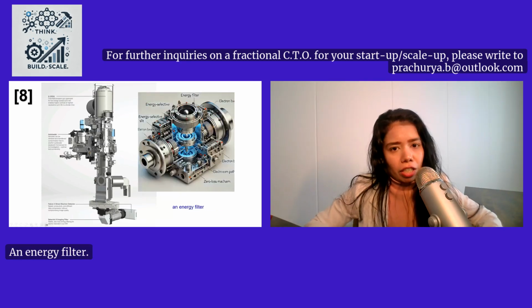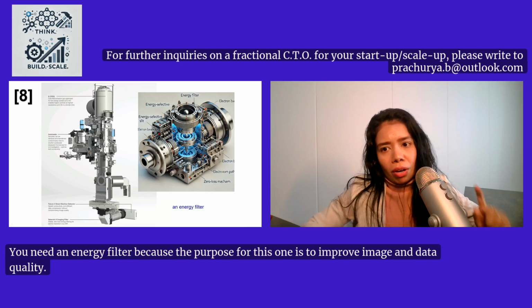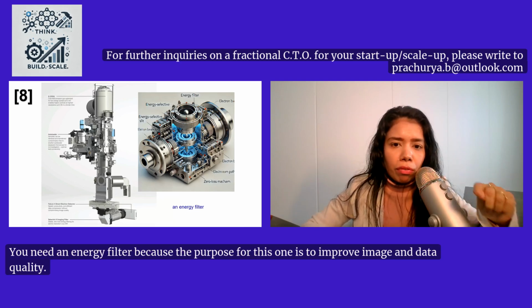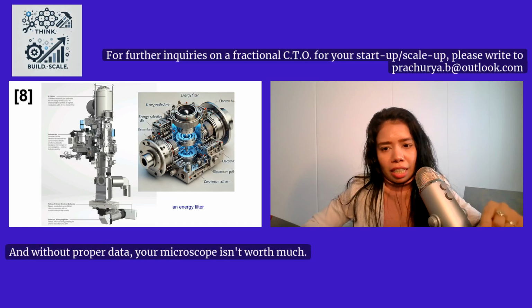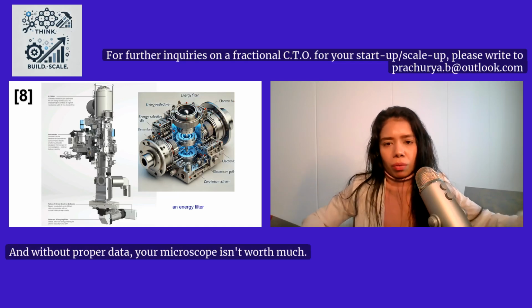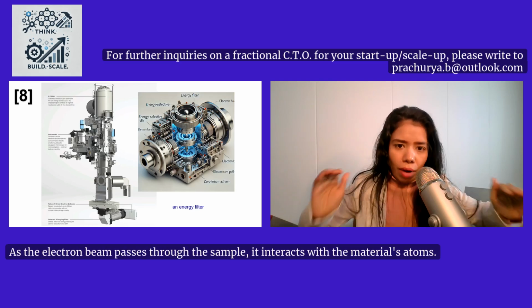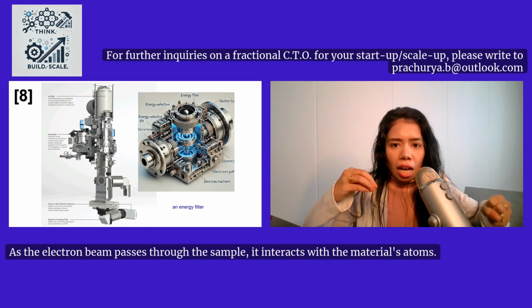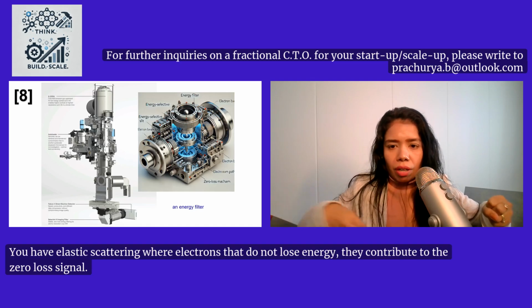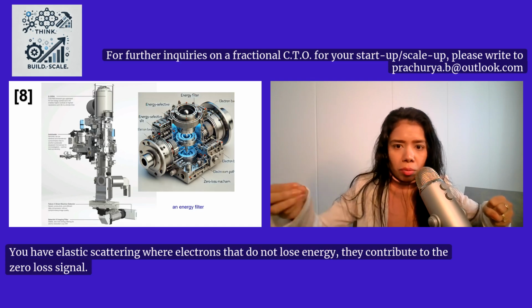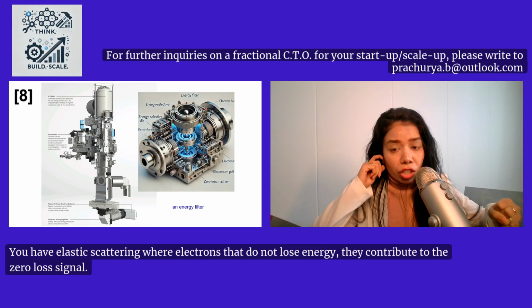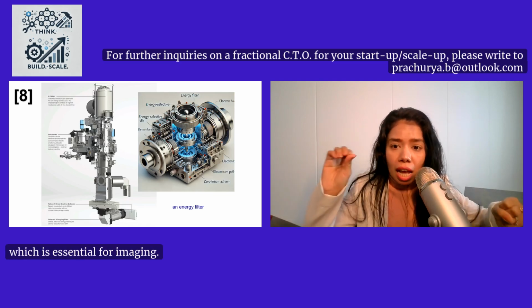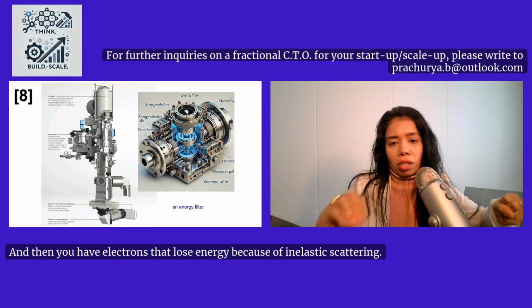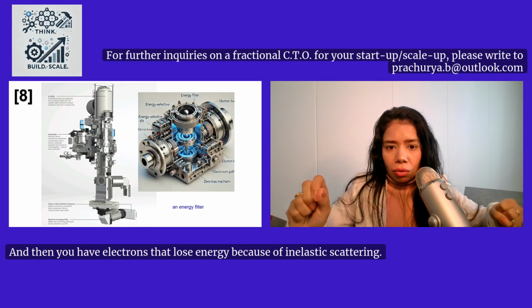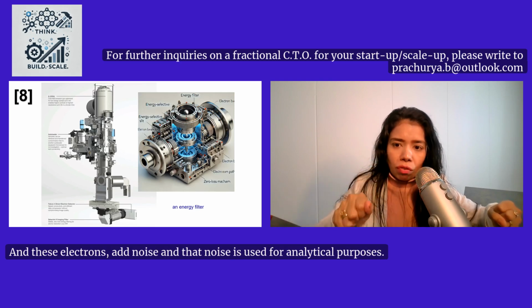An energy filter. You need an energy filter because the purpose for this one is to improve image and data quality. And without proper data, your microscope isn't worth much. How does it work? As the electron beam passes through the sample, it interacts with the material's atoms. You have elastic scattering, where electrons that do not lose energy contribute to the zero loss signal, which is essential for imaging. And then you have electrons that lose energy because of inelastic scattering, and these electrons add noise, and that noise is used for analytical purposes.